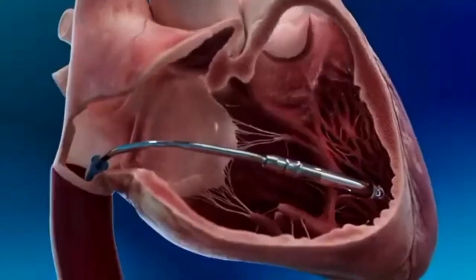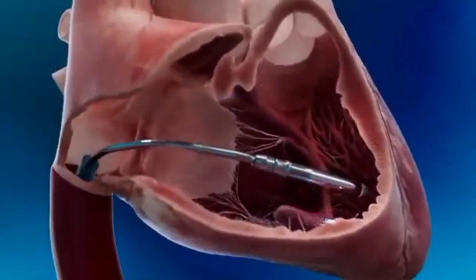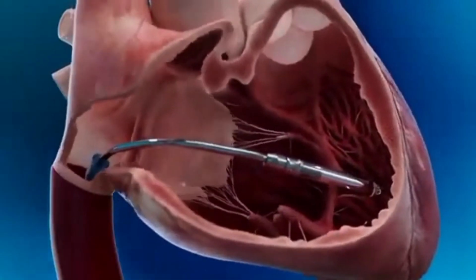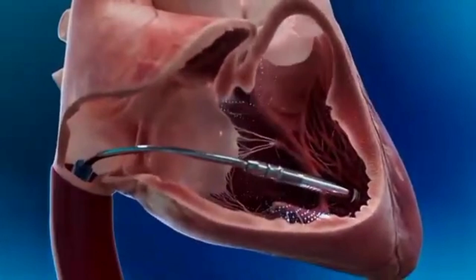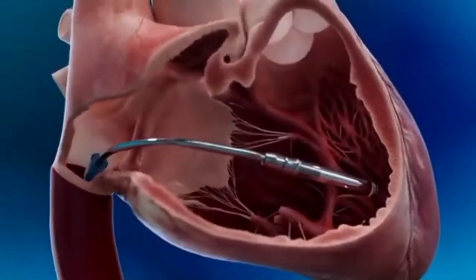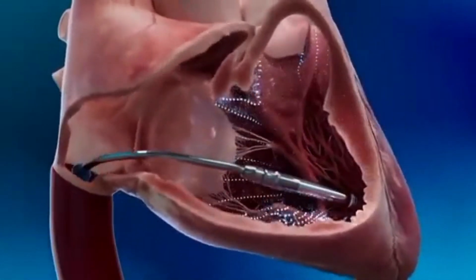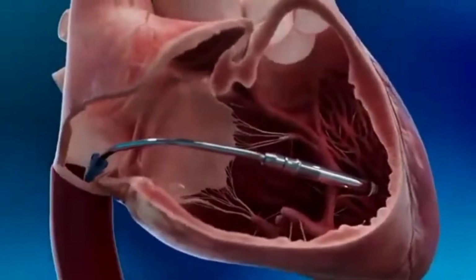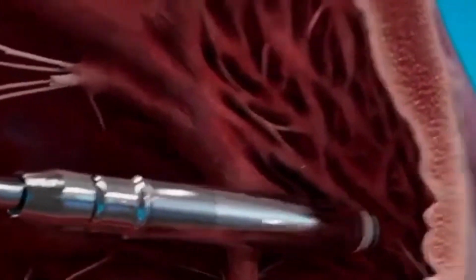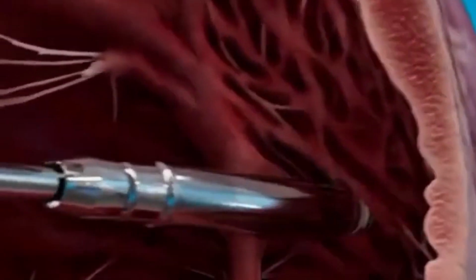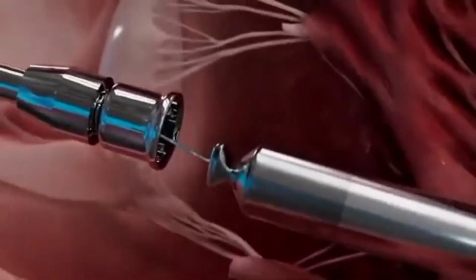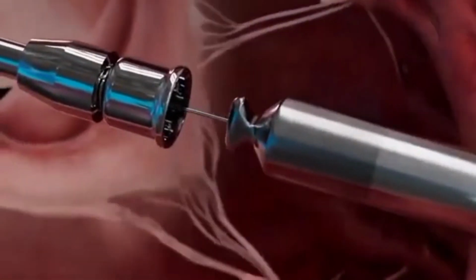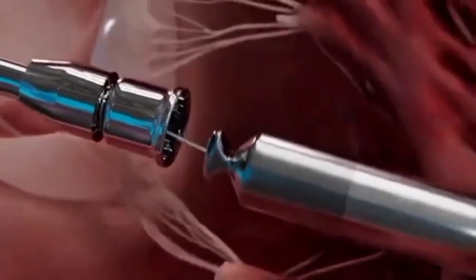While mapping, the device can measure R waves, impedance, and an initial capture threshold before fixation by simply touching the leadless pacemaker's tip electrode to the endocardial tissue. Again, the purpose is to find the ideal location for the pacemaker. The device is then turned, which engages the helix into the soft tissue. The catheter is placed into tether mode to allow for final testing. When testing is satisfactory, the device is released.